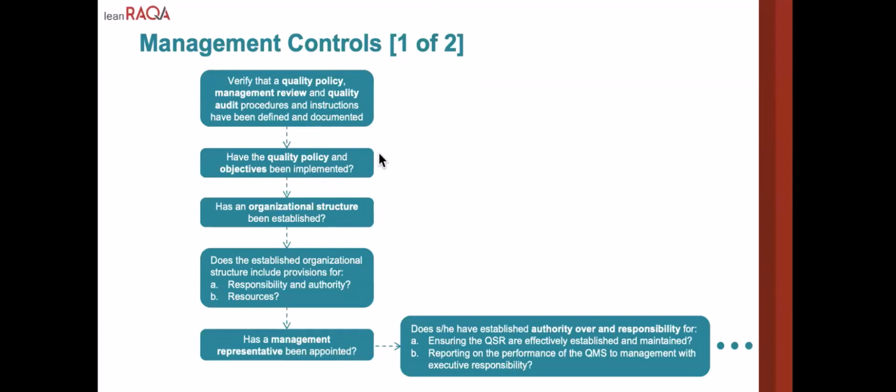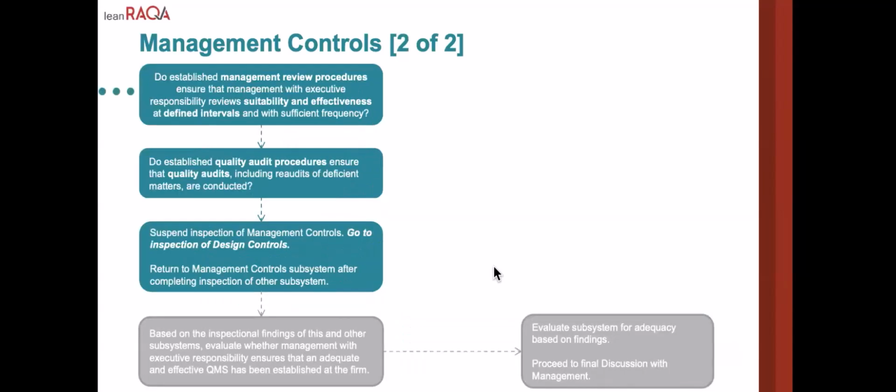You give evidence, then the FDA will either think it meets what they ask for, ask another question, or decide it doesn't meet, and they may go down a different leg of the flow chart. Eventually they take the evidence they've gained down to this point, and then they go do the reality check in other subsystems.